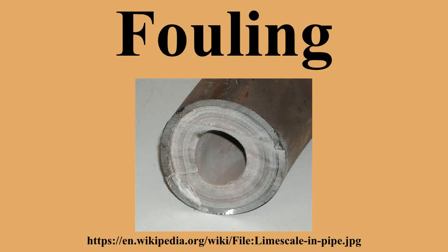Blowdown capability is always incorporated into steam generators or evaporators to control the accumulation of non-volatile impurities that cause or aggravate fouling. Low fouling surfaces are an option for some applications. Modern components are typically required to be designed for ease of inspection of internals and periodic cleaning. Online fouling monitoring systems are designed for some applications so that blowing or cleaning can be applied before unpredictable shutdown is necessary or damage occurs.